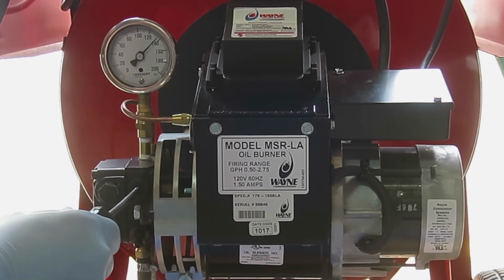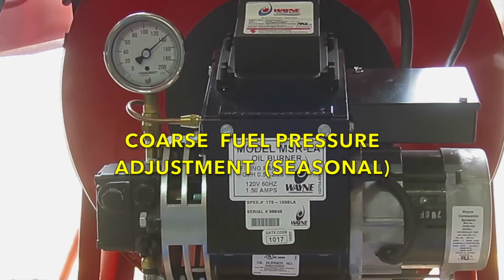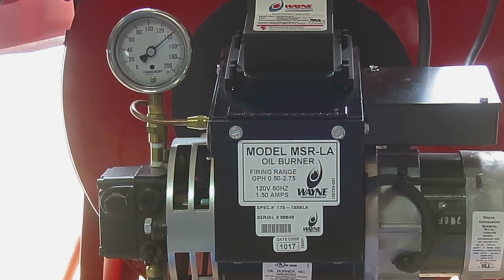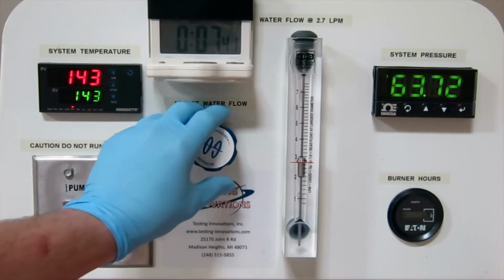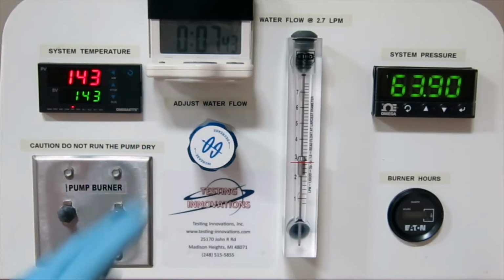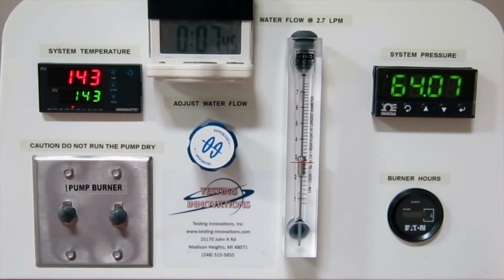If you start out calibrating with the warmer water from inside the pipes in your facility, you will definitely encounter drift shortly. At some point, the newer incoming water will be colder. If you have not established the groundwater temperature before reaching the calibration process, this may create some difficulty for you. This new condition will change the wand output.